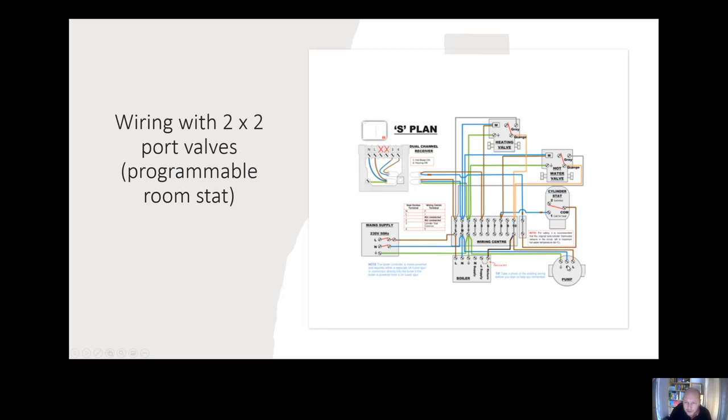There should be a slight overrun on the pump, and the reason for that is to allow it to take any extra heat out of the boiler, and that's actually one of the reasons why we should fit a bypass, because it could cause damage to the pump. If the pump's trying to pump and this heating valve is closed, then that's obviously an issue.